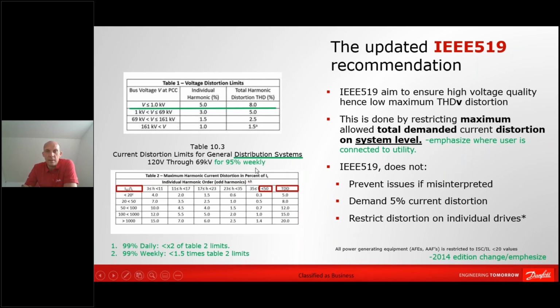So that's some of the updates the recommendation has given in the newest update that we saw in 2014 on IEEE 519. But it is important to notice that this is a system level demand and not at individual component level. So the 5% current distortion in IEEE 519 doesn't apply to one single load on your transformer. It's for the combined loading of your transformer.